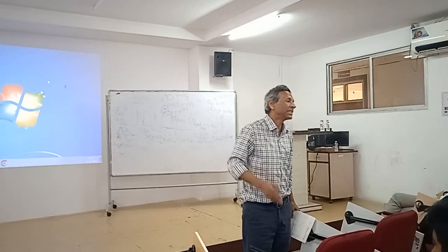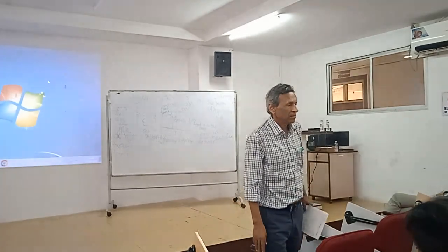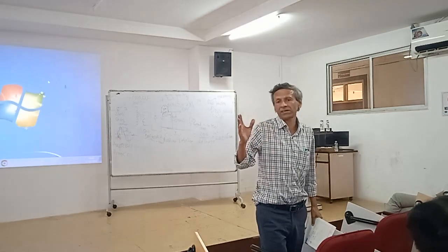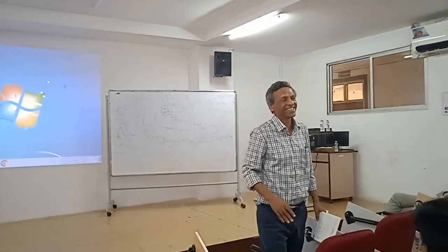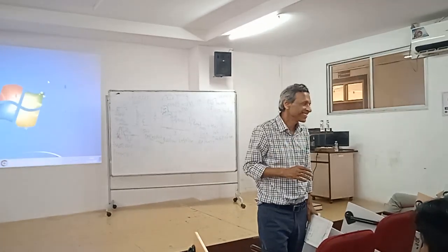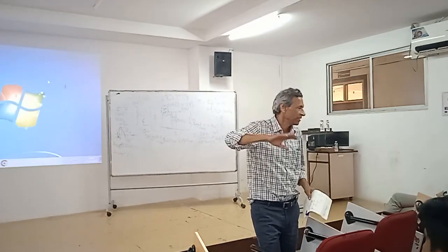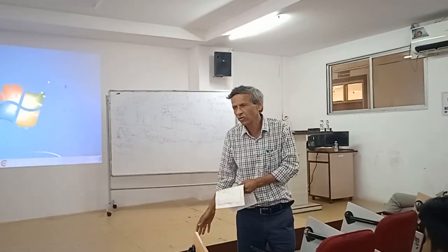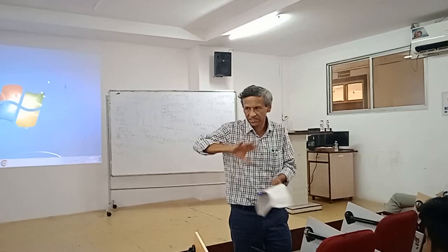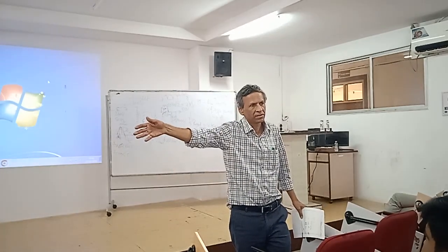So far as the GEB transformer is concerned, the harmonic will not be going to the high tension side. Suppose GEB has a delta star transformer, 11,000 volt to say 415 volt. Delta star is required because single phase load may be served, three phase load may be served.